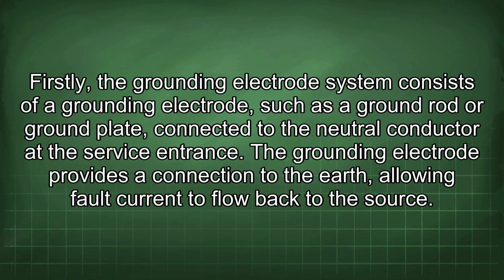Firstly, the grounding electrode system consists of a grounding electrode, such as a ground rod or ground plate, connected to the neutral conductor at the service entrance. The grounding electrode provides a connection to the earth, allowing fault current to flow back to the source.